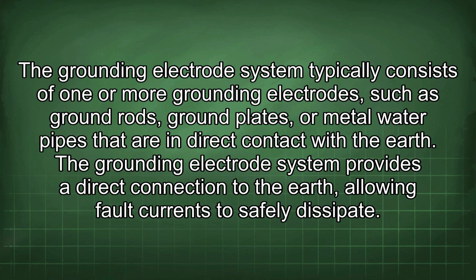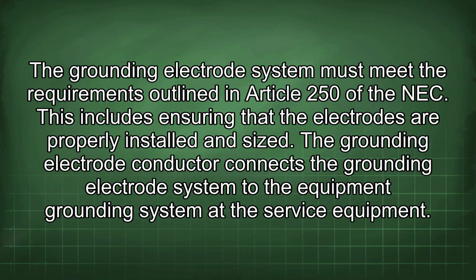The grounding electrode system typically consists of one or more grounding electrodes, such as ground rods, ground plates, or metal water pipes that are in direct contact with the earth. The grounding electrode system provides a direct connection to the earth, allowing fault currents to safely dissipate. The grounding electrode system must meet the requirements outlined in Article 250 of the NEC. This includes ensuring that the electrodes are properly installed and sized.